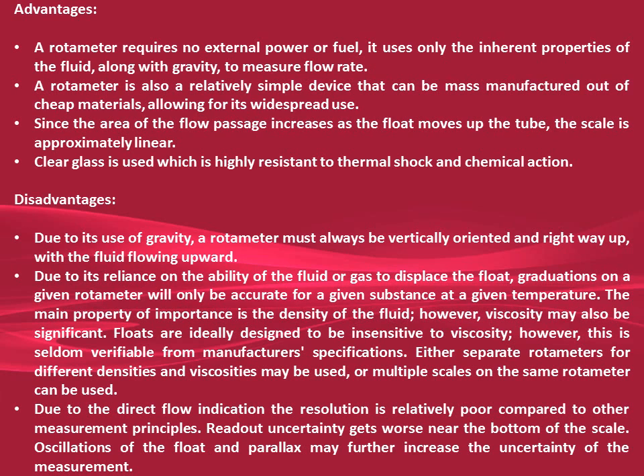DISADVANTAGES: Due to its use of gravity, a rotameter must always be vertically oriented and right way up, with the fluid flowing upward. Due to its reliance on the ability of the fluid or gas to displace the float, graduations on a given rotameter will only be accurate for a given substance at a given temperature.